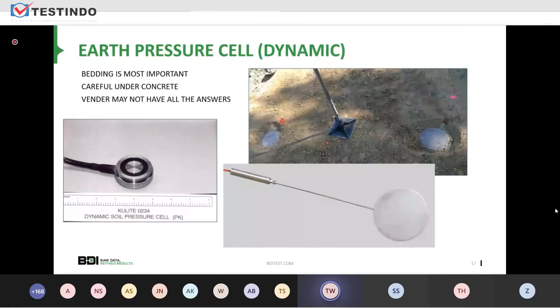So it's kind of a tricky installation, and you should follow manufacturer's procedures, and you can make other improvements along the way, because most vendors really don't actually go out to the field and install these. So they give the best installation recommendations, but there are a number of techniques that we've come across from our actual physical installations that improve our survivability and our measurability from these pressure cells. So here are 2 instances for pressure cells that you need to be aware of.